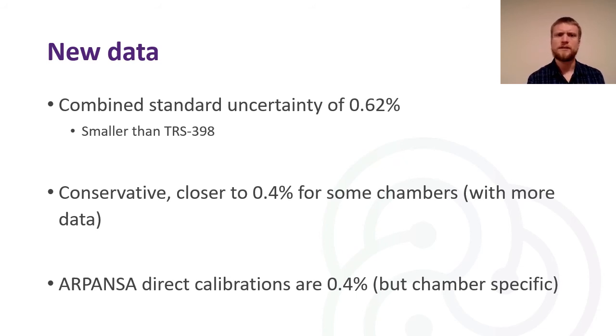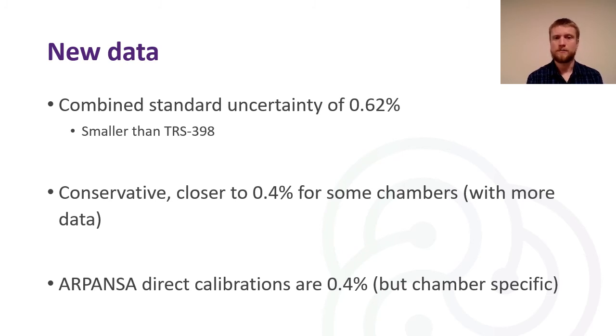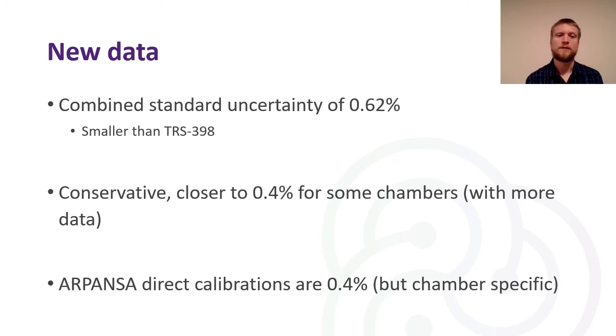This is a conservative uncertainty. We see closer to 0.4% for some chambers that have more data in the data set. The ARPANSA direct calibration standard uncertainty is 0.4%, which is lower, and very importantly the direct calibration service allows you to have KQ values generated for your specific chamber, not for a generic chamber of that type.